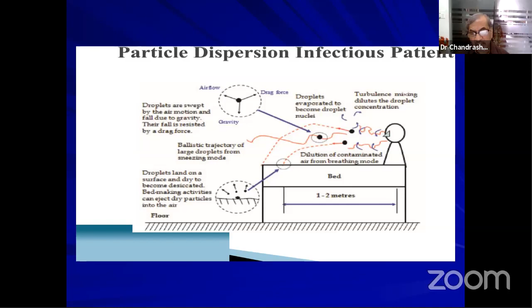Then we decided to at least use ultraviolet germicidal irradiation, the known technology, in the duct or in the coil, and even upper-room UVGI, which you used to use in the TB wards in earlier cases. You have to be very careful that UV radiation should not be directly exposed to any human being, for the safety of the skin and the eyes. So it has to be handled very carefully with the help of an expert, not that anybody can put in UVGI as such. And we use this UVGI setup in the air handling unit.